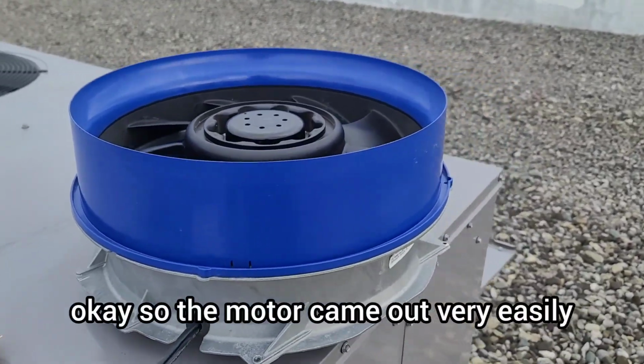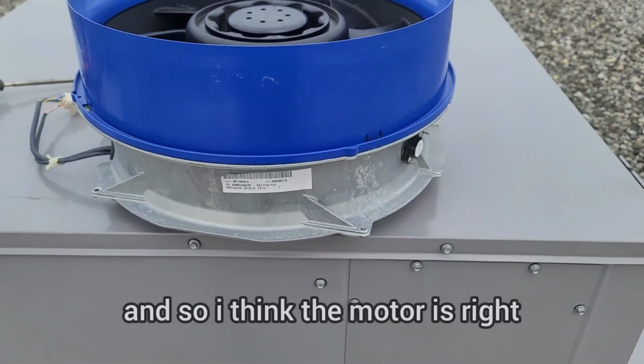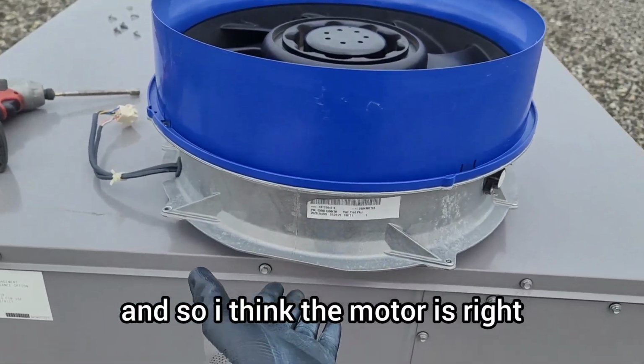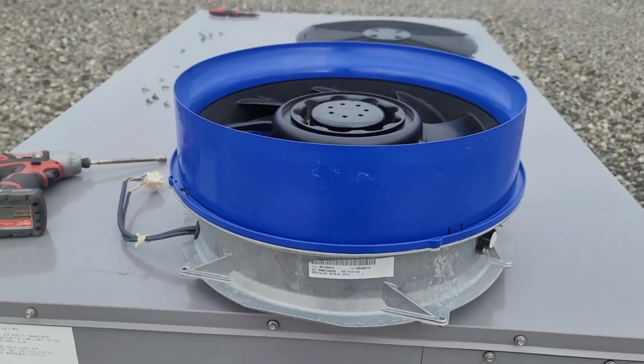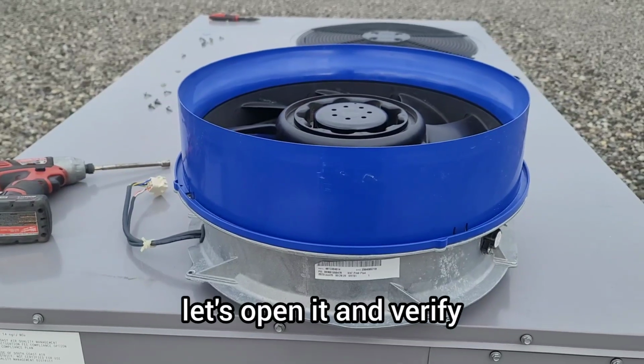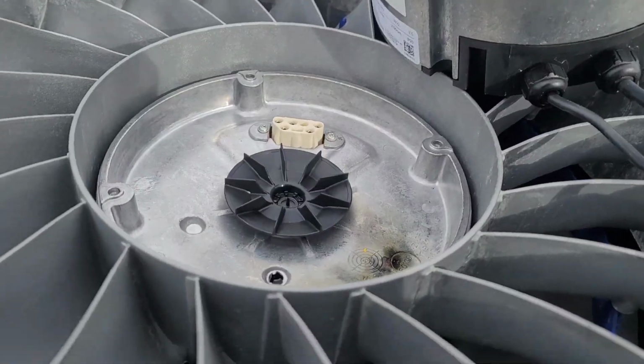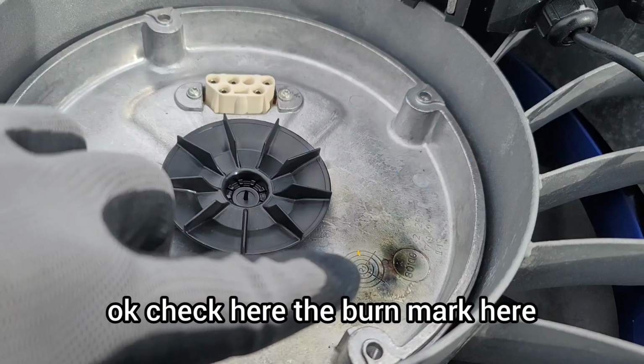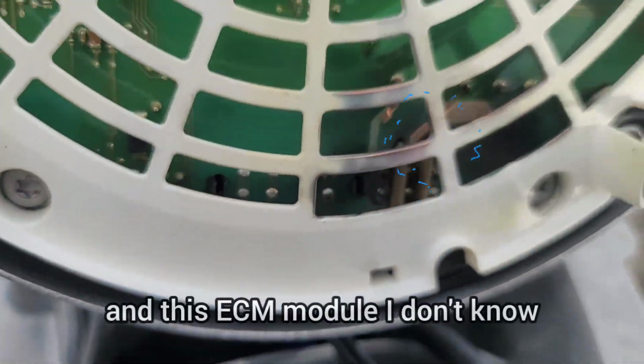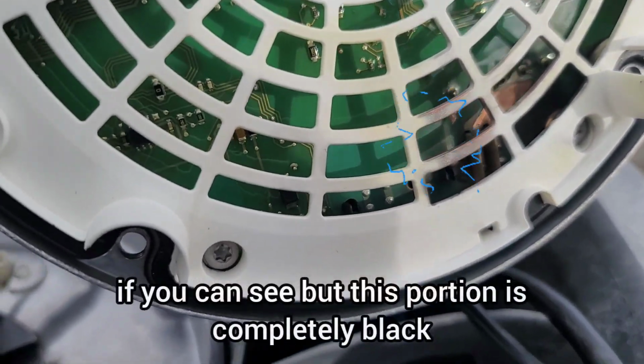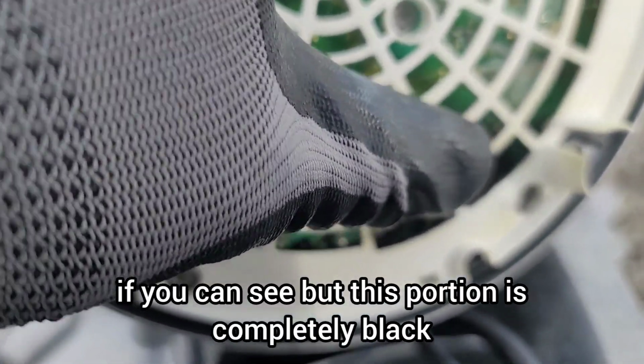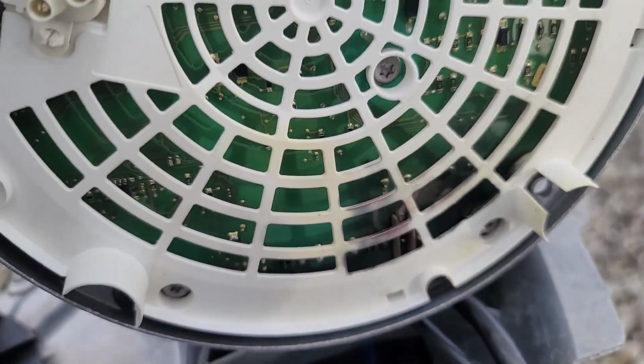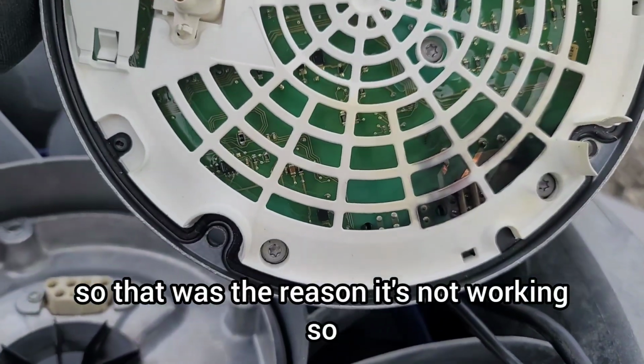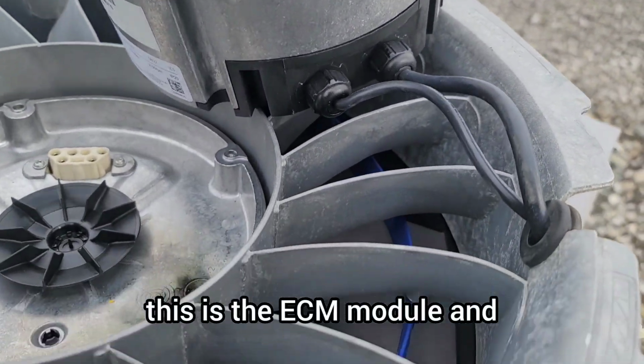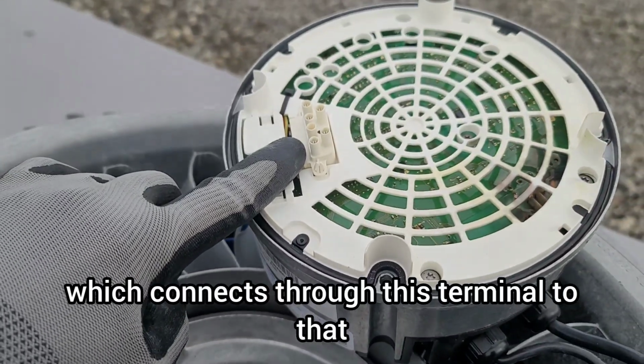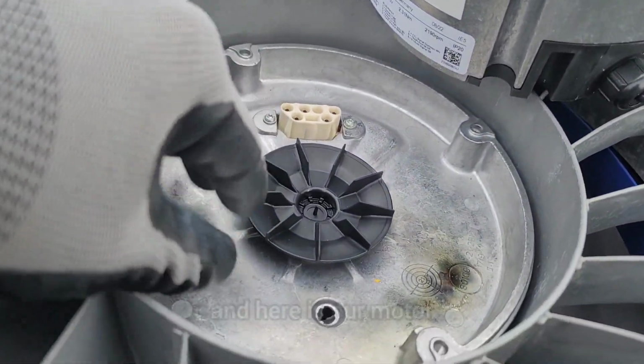Okay, so the motor came out very easily, and I think the motor is right underneath. Let's open it and verify what is going on. Okay, check here the burn mark, and this ECM module, I don't know if you can see, but this portion is completely black, burnt. So that was the reason it's not working. So this is the ECM module, which connects through this terminal to that, and here is our motor.